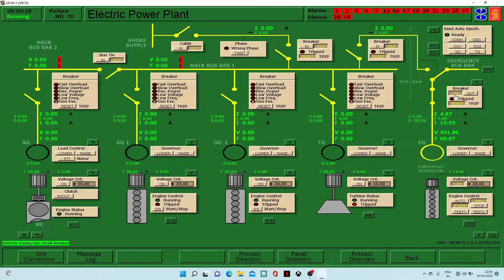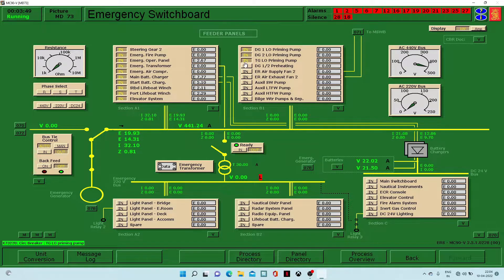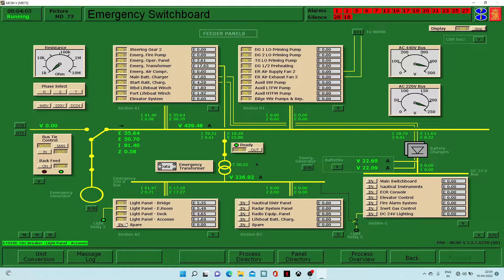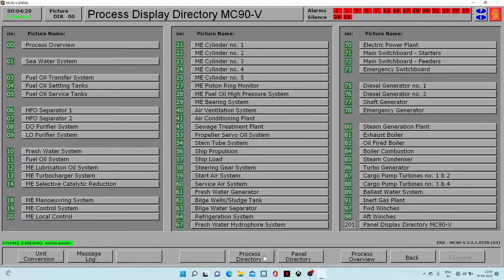Now we will give the supplies going from the emergency switchboard. In the lab we have to do all this within 20 minutes. We have to silence all the alarms. The red indicator is for the transformer — it steps down the voltage. We will now turn on these pairs from the top; 440 volts is converted with the help of this transformer into 220 volts. The other one is the rectifier battery charger. So our emergency generator work is now over, and we are ready to start diesel generator one.